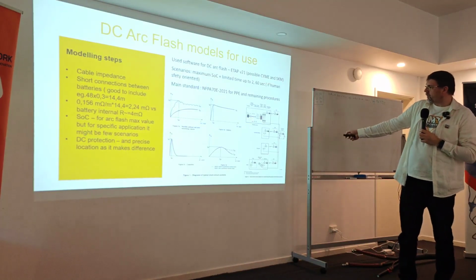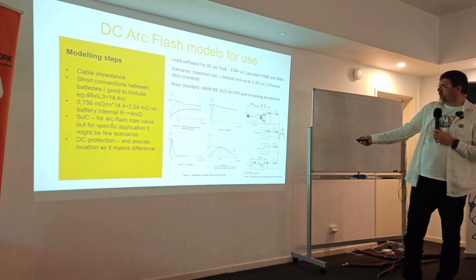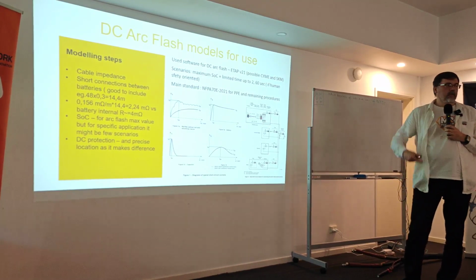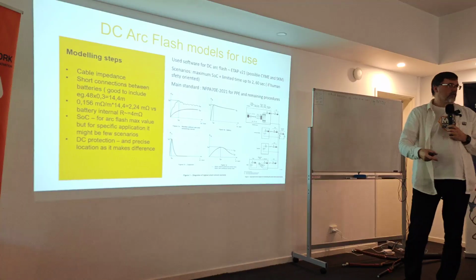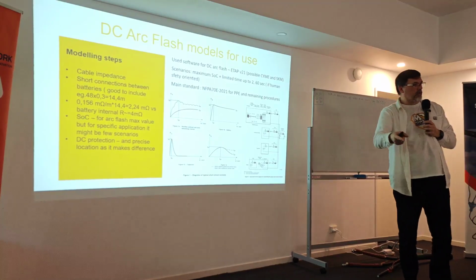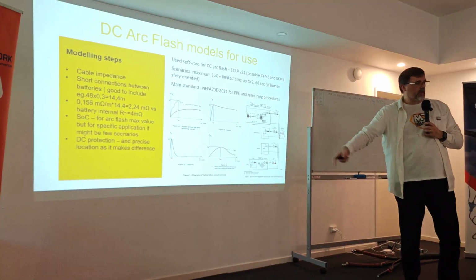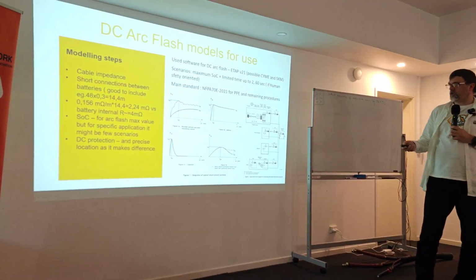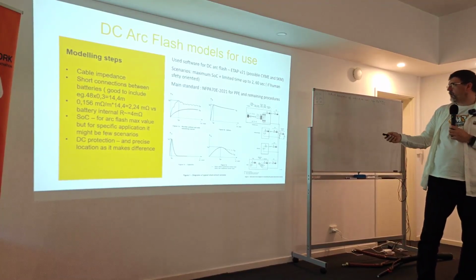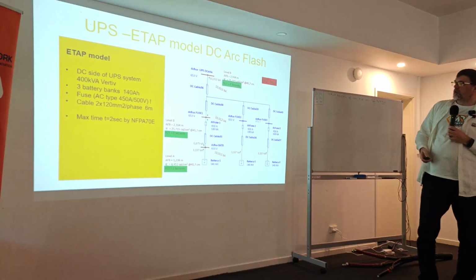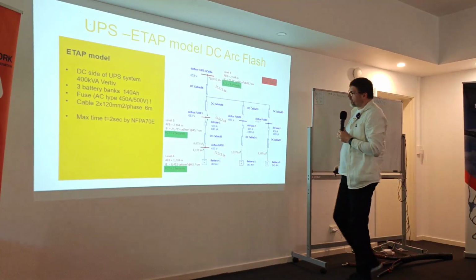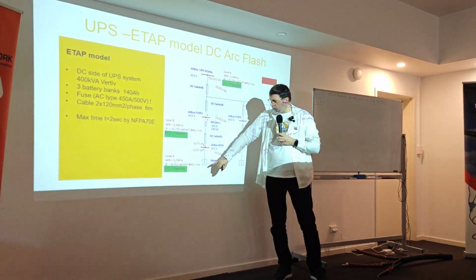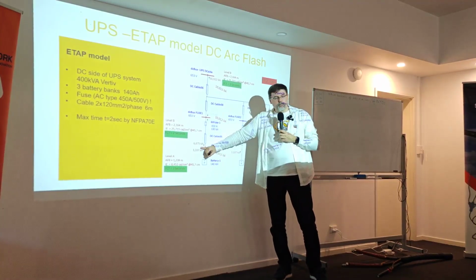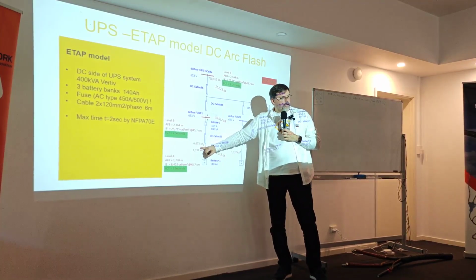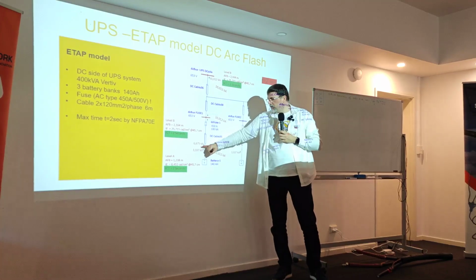So this is how you create the models technically by the standard. When you would like to create a DC model for your short circuit calculation, because we need the short circuit calculation to go to protection and arc flash later, which is 61660 if I remember correctly. It's a different model. This was modeled in ETAP. We have a battery, and this is the calculation point for the battery itself, let's say the entrance of the battery.